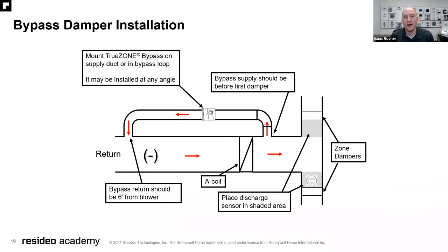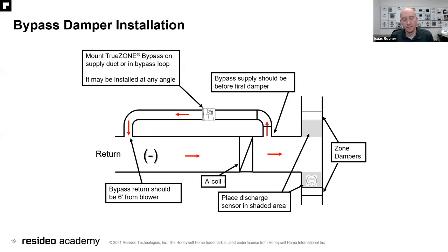Where do we install the bypass damper? We should mount the true zone bypass on the supply duct or in a bypass loop. It can be installed conveniently at any angle. The most important thing is that the bypass supply should be before the first damper, and the return should be six feet from the blower. You can also see here where we typically place the discharge air sensor, which is shown in the bottom right — good for reference as well.